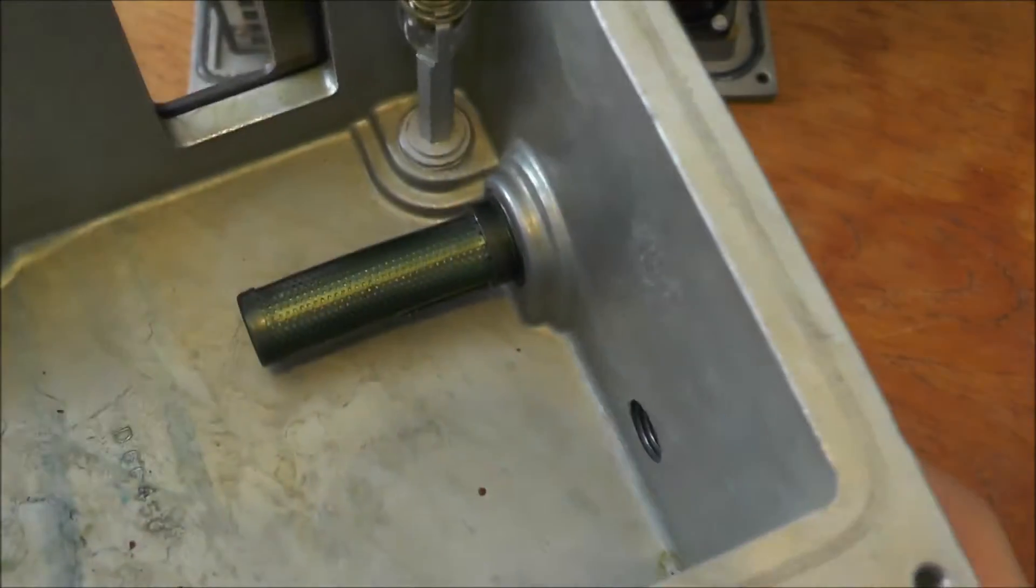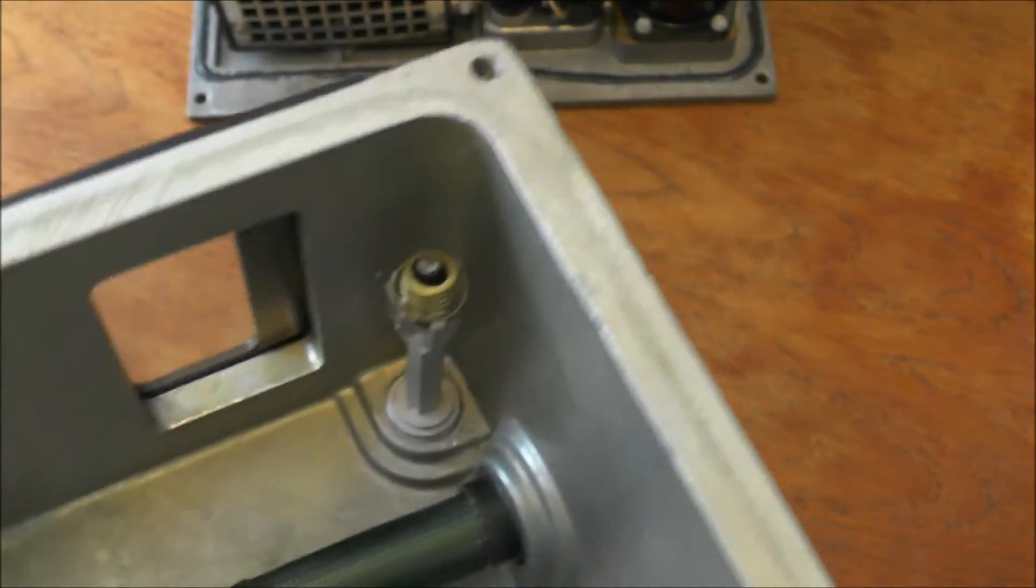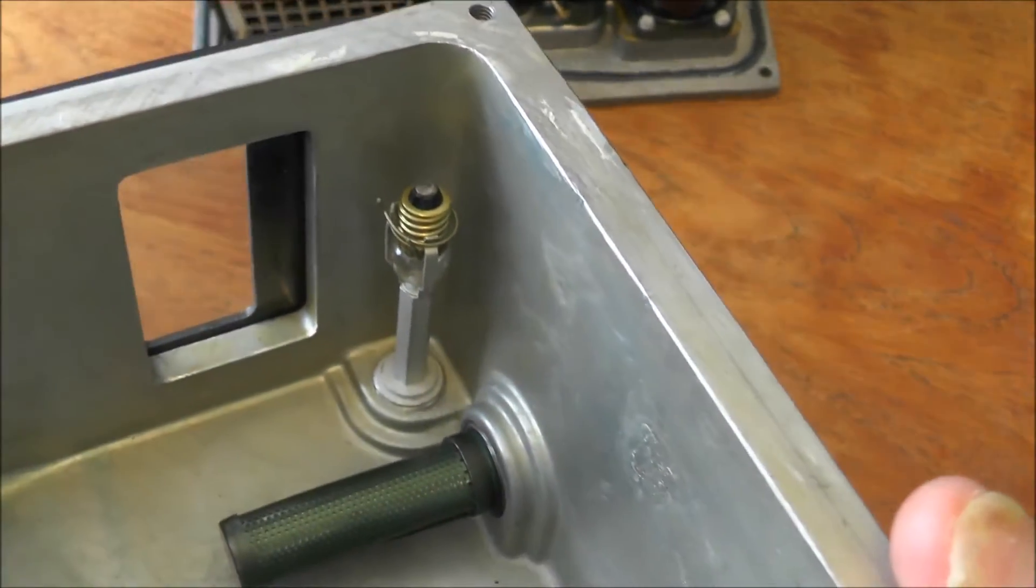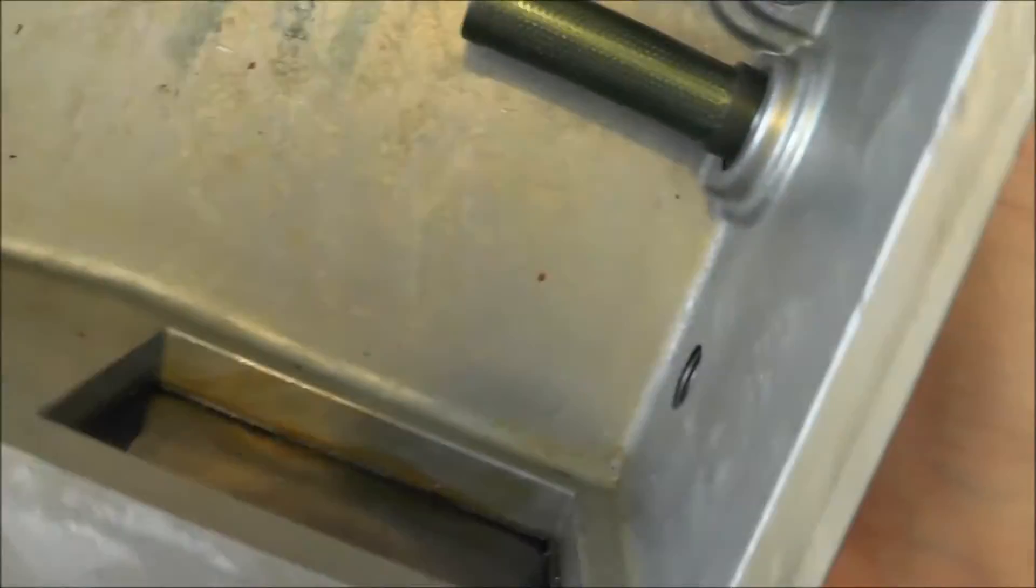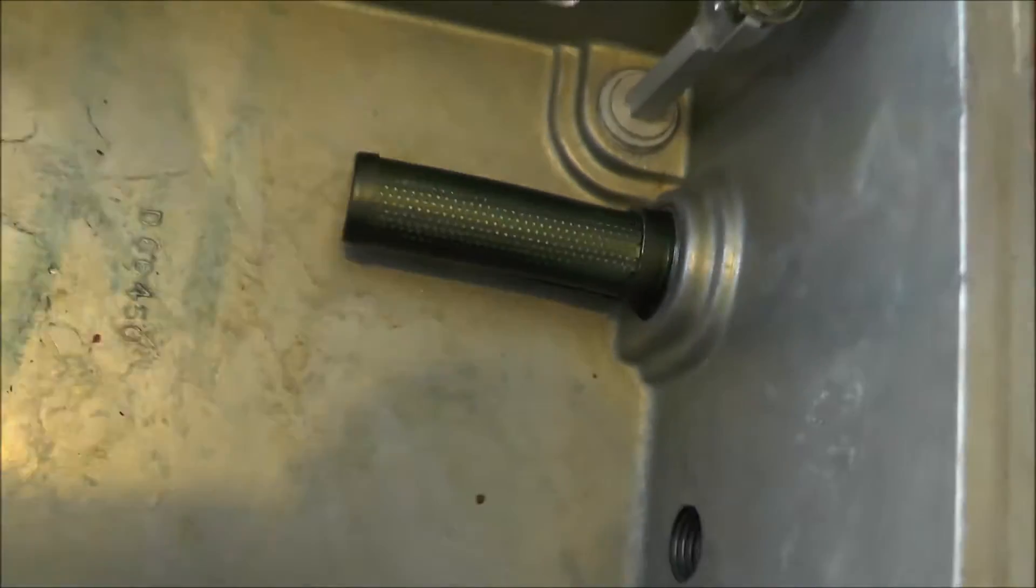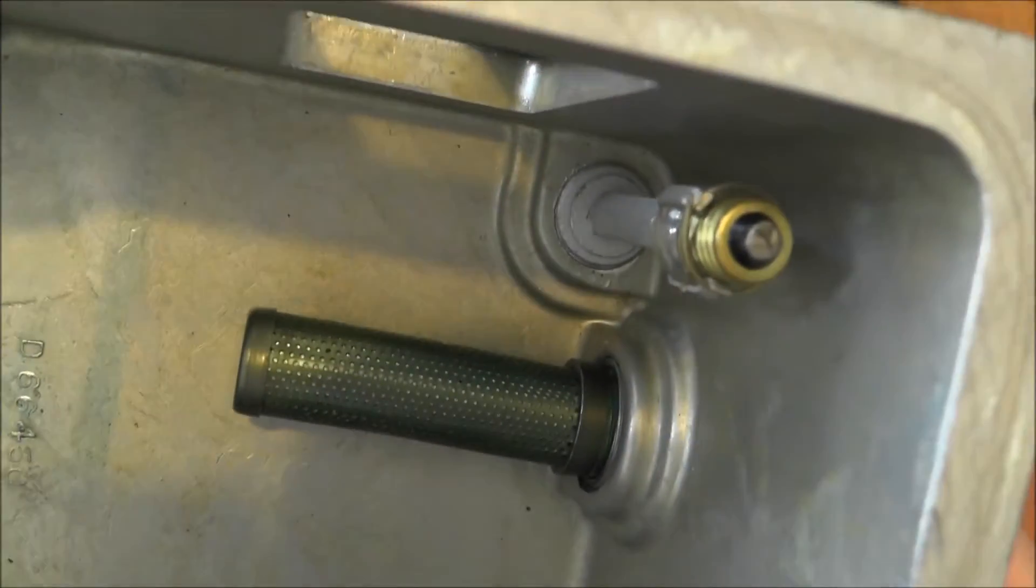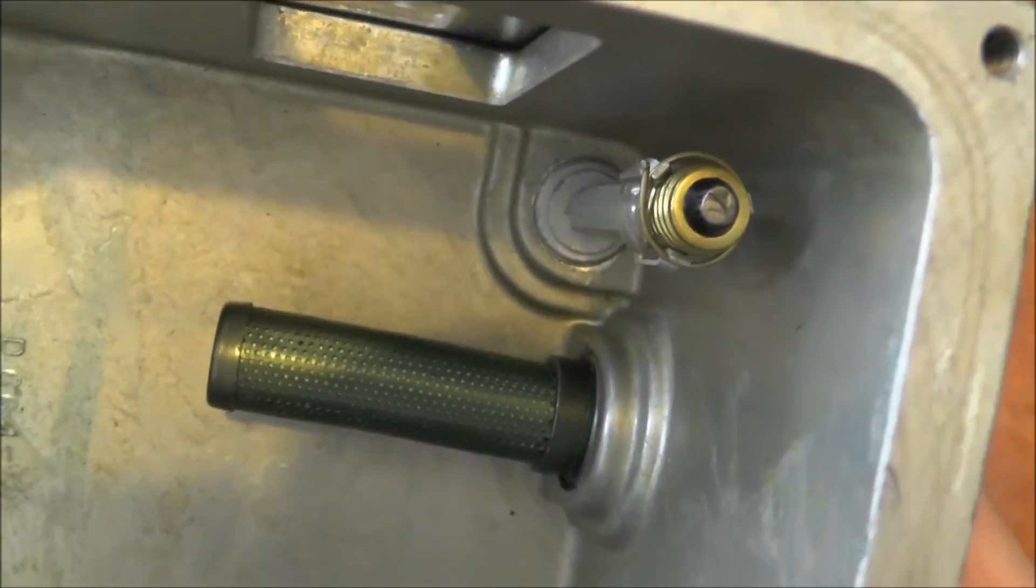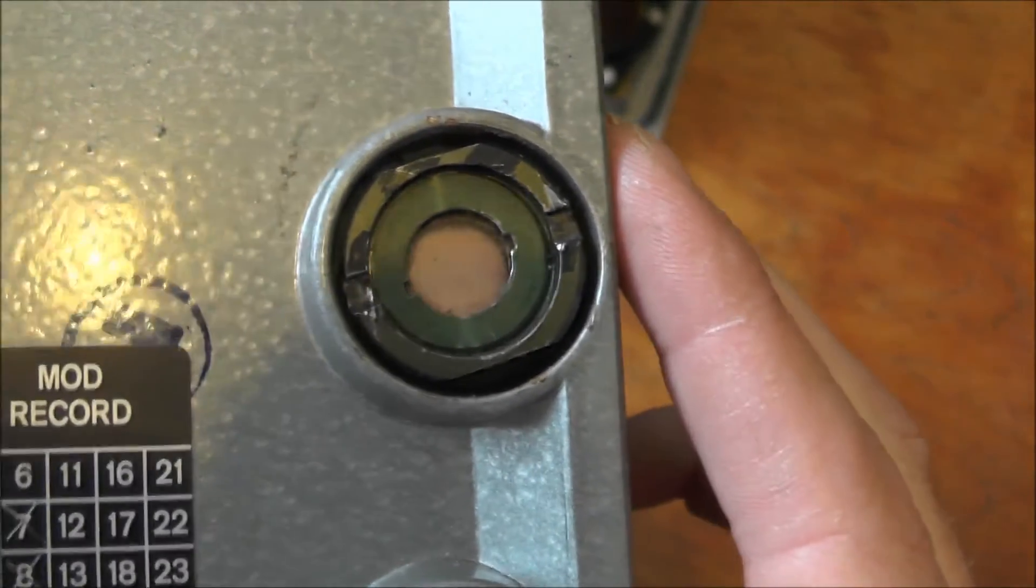So what we can see inside there is the lamp for the display that makes contact with that. The other component there, that is a silica gel pack and a moisture meter which changes color on the indicator on the end when it's absorbed a certain amount of moisture. Then it needs to be replaced.